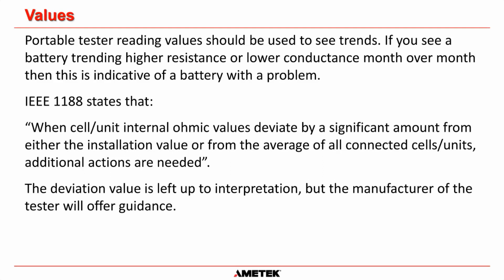Now, the IEEE standard for valve regulated batteries is 1188, and that states that when a cell or unit internal ohmic value or internal resistance deviates by a significant amount from either the installation value or from the average of all connected cells or units, additional actions are required. That deviation is left up to interpretation. There is no official industry standard, but the manufacturer of the tester will offer guidance. Usually they say 125% of baseline means you need to look into things further, perhaps perform a capacity test, and 150% maybe you need to replace the jar. But once again, it is left to interpretation.